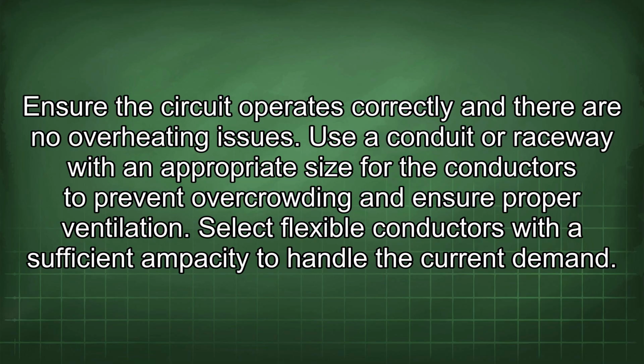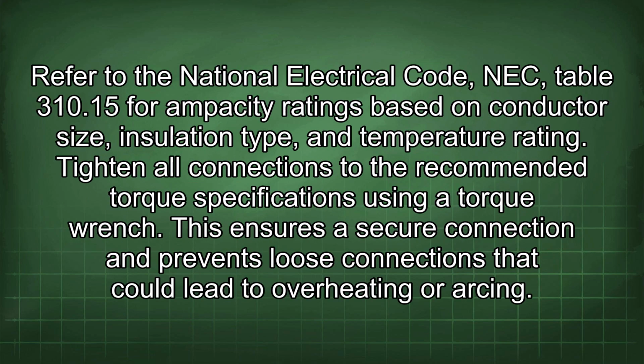Use a conduit or raceway with an appropriate size for the conductors to prevent overcrowding and ensure proper ventilation. Select flexible conductors with a sufficient ampacity to handle the current demand. Refer to the National Electrical Code, NEC, Table 310.15 for ampacity ratings based on conductor size, insulation type, and temperature rating. Tighten all connections to the recommended torque specifications using a torque wrench. This ensures a secure connection and prevents loose connections that could lead to overheating or arcing.